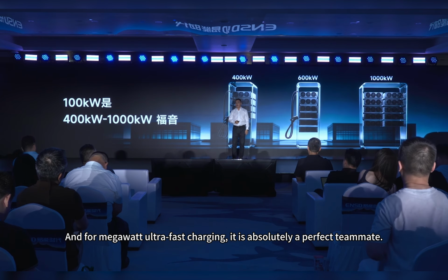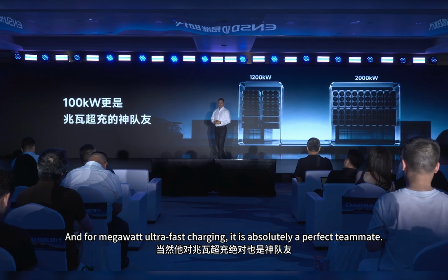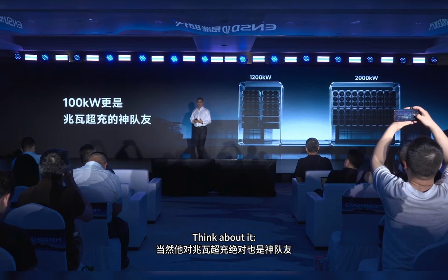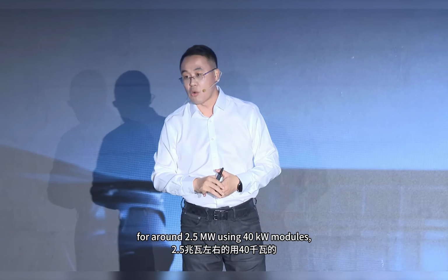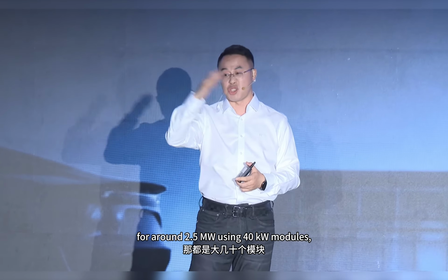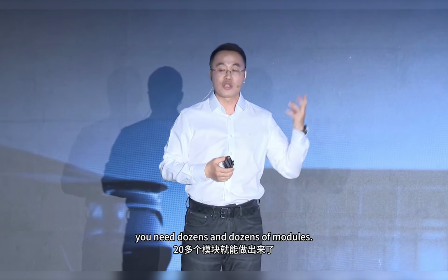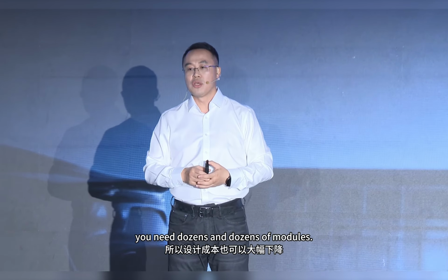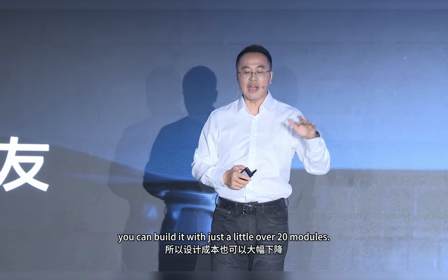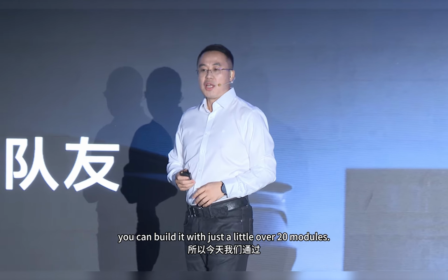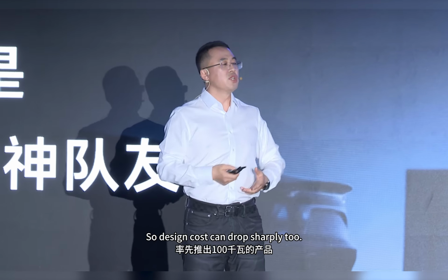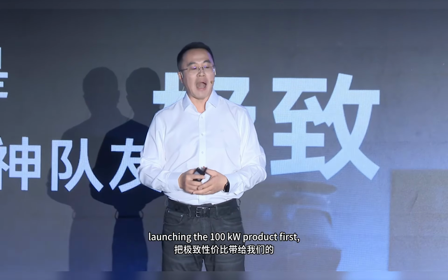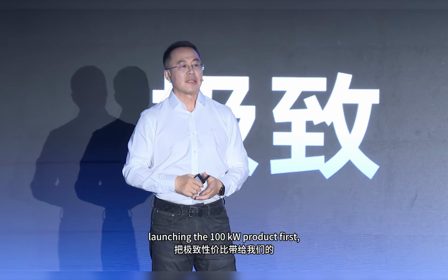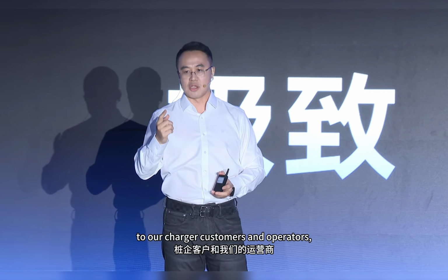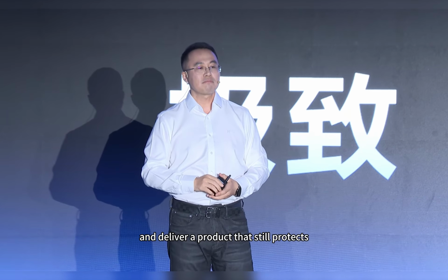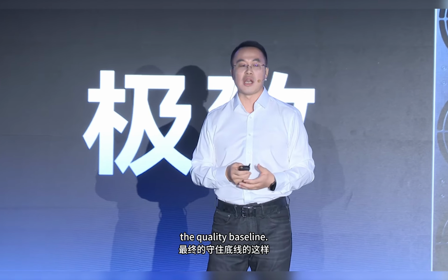And for megawatts ultra-fast charging, it is absolutely a perfect teammate. Think about it. For around 2.5 megawatts using 40 kilowatts modules, you need dozens and dozens of modules. Now with this, you can build it with just a little over 20 modules. So design costs can drop sharply. Today, by launching the 100 kilowatts product first, we bring outstanding value to our charger customers and operators and deliver a product that still protects the quality baseline.